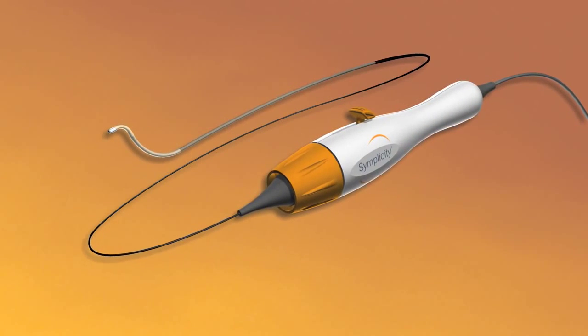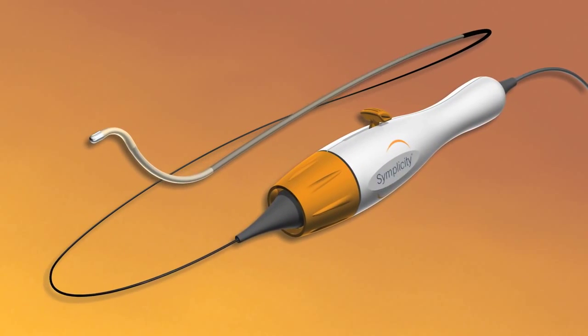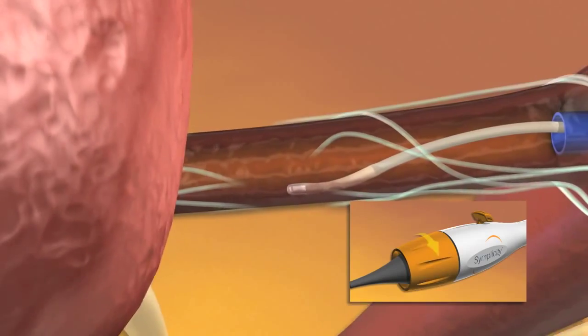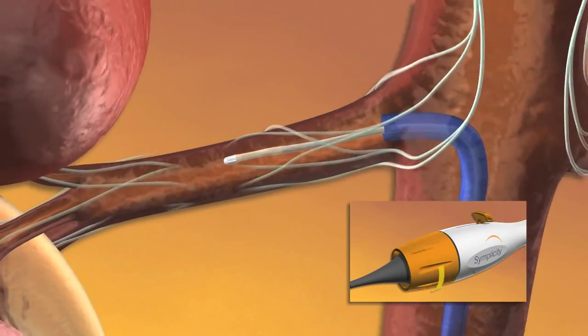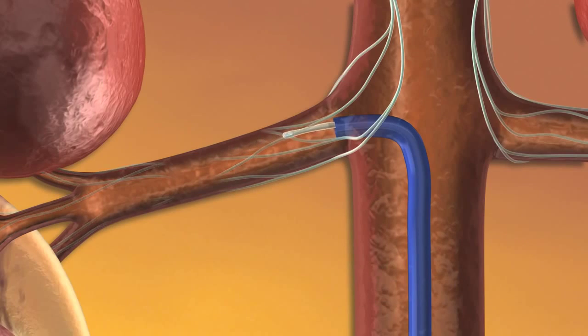The Ardian Symplicity Catheter System offers physicians a way to precisely target and deactivate renal nerves with controlled low-power RF energy delivery from the tip of the catheter through the artery walls to the surrounding renal nerves. This novel intervention is intended to reduce the level of sympathetic nervous system hyperactivity and lower blood pressure.